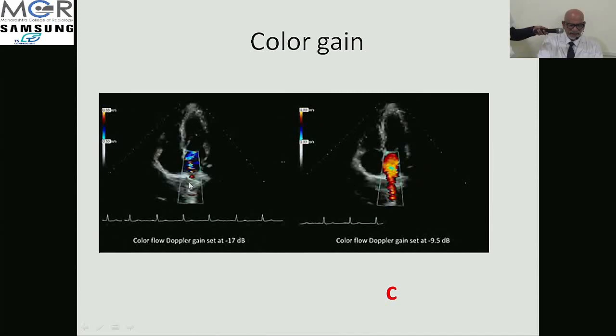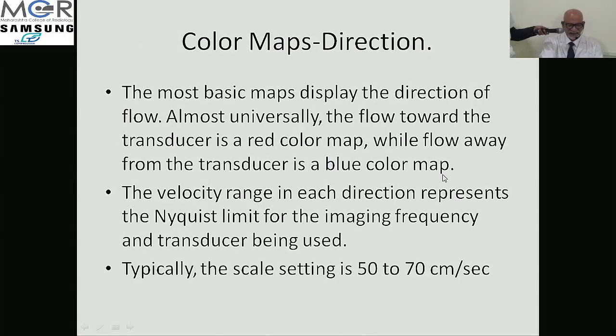But here color gain was less, so everything is lost except this very minimal flow that is being seen over here. So the adjustment of color gain will make a lot of difference. Now, color maps. The most basic maps display the direction of the flow. Almost universally, the flow towards the transducer is red, while flow away from the transducer is blue. This is the universal color code. But if you want, you can change it.